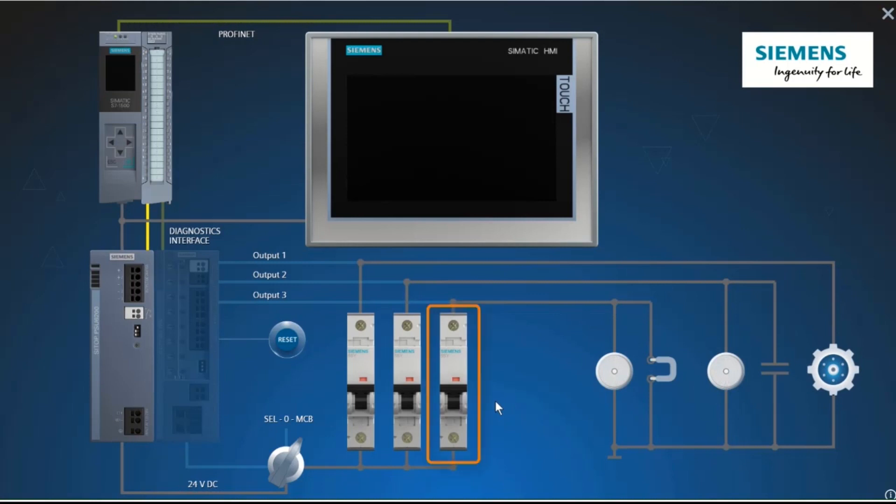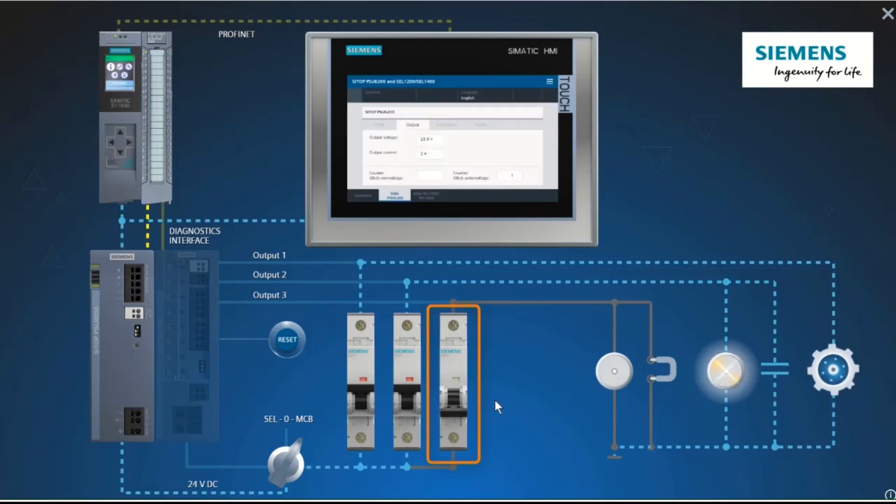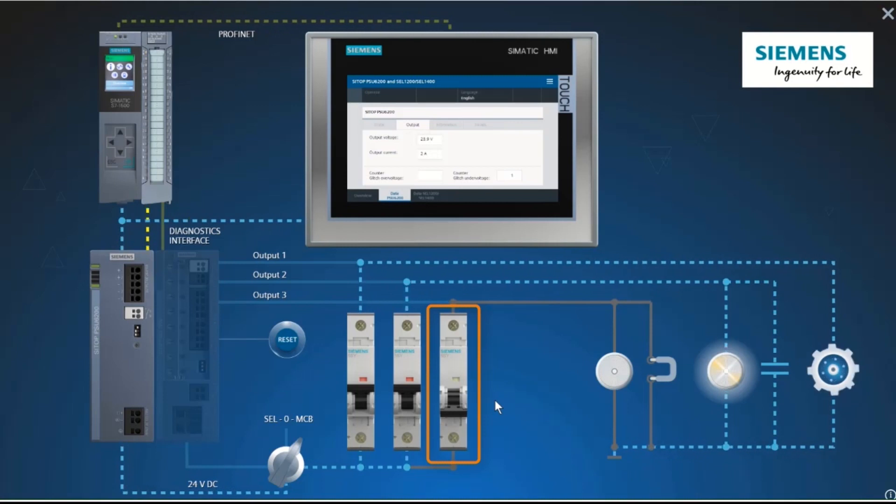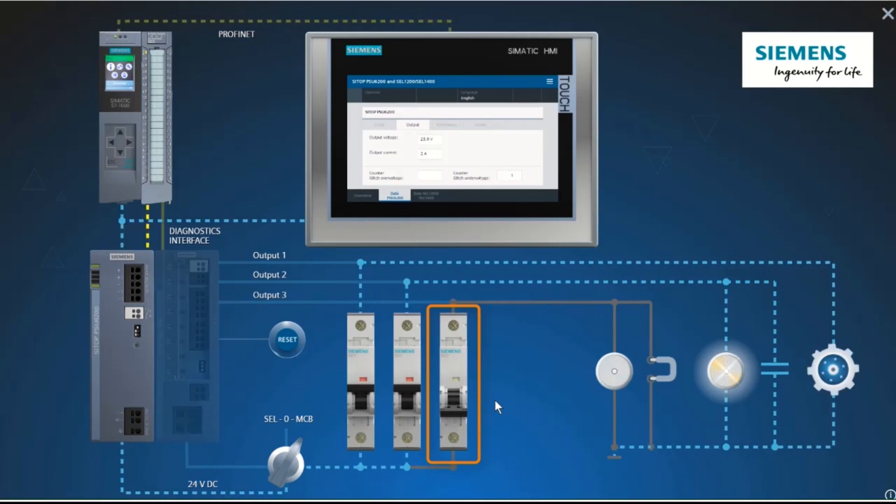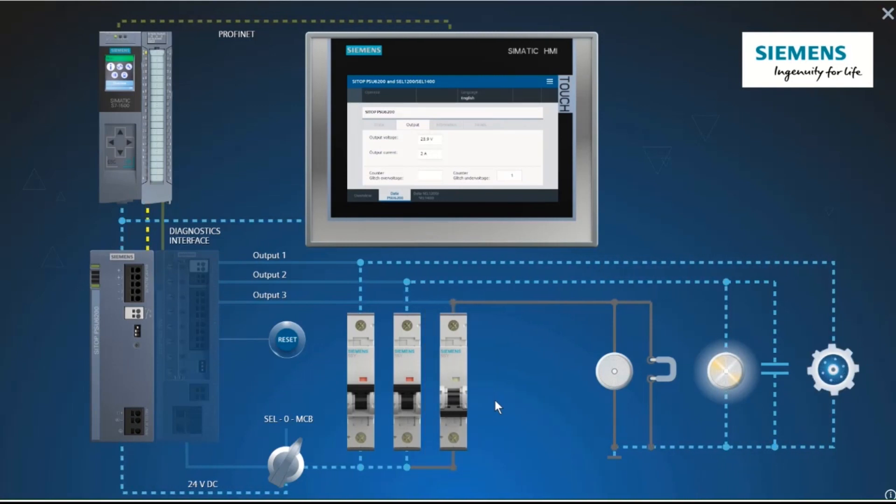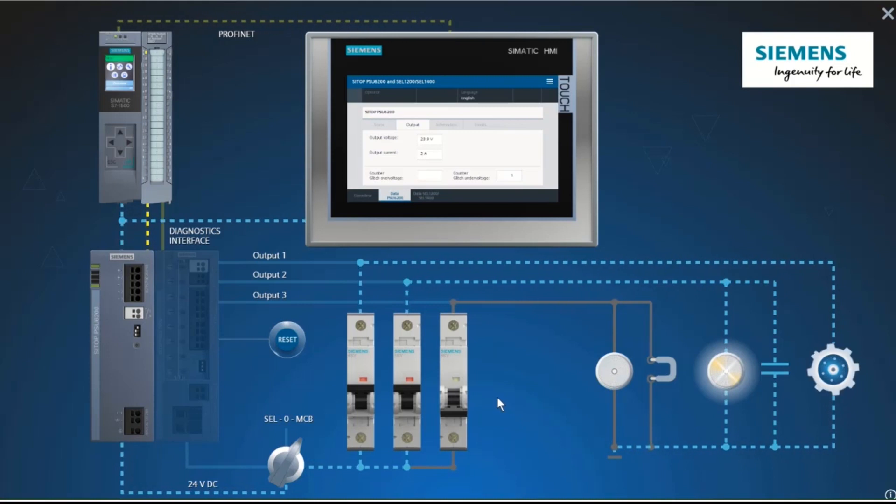As you can see, the miniature circuit breaker does not trip immediately. The voltage has dropped and the PLC has gone to stop. The whole system has come to a standstill.